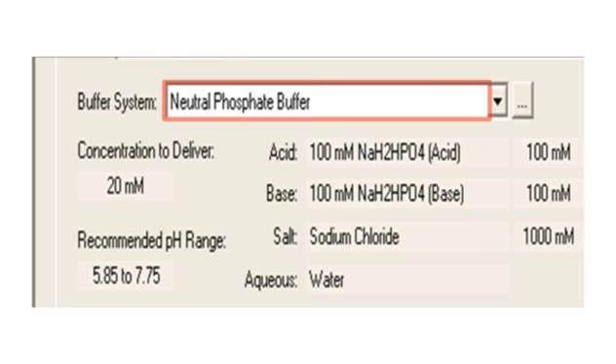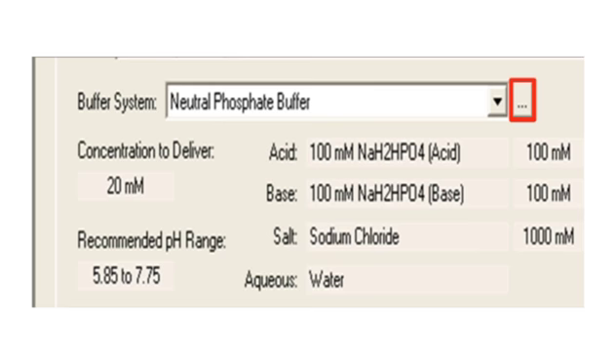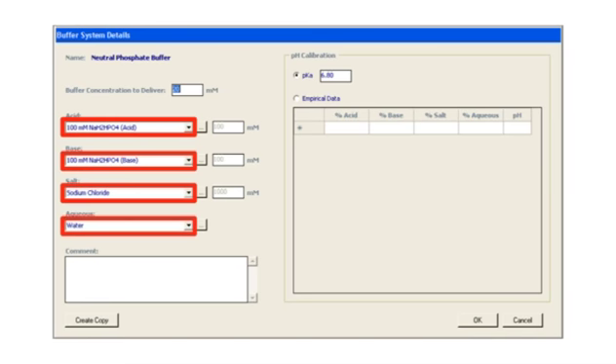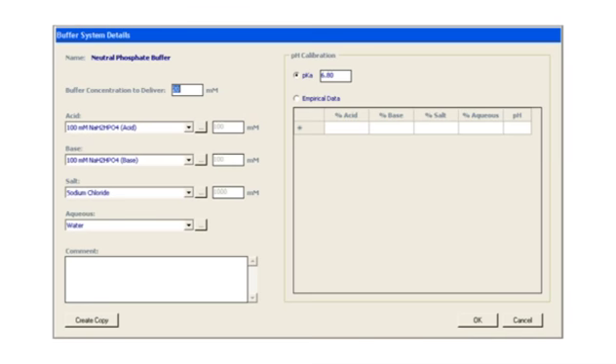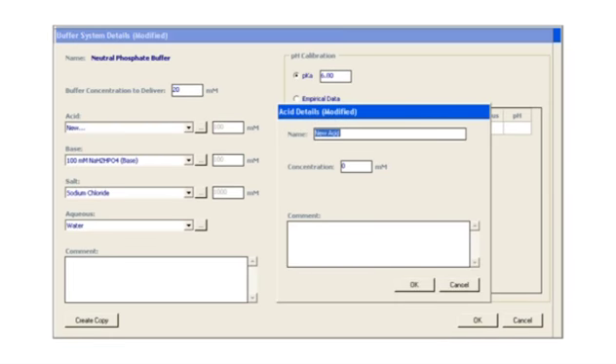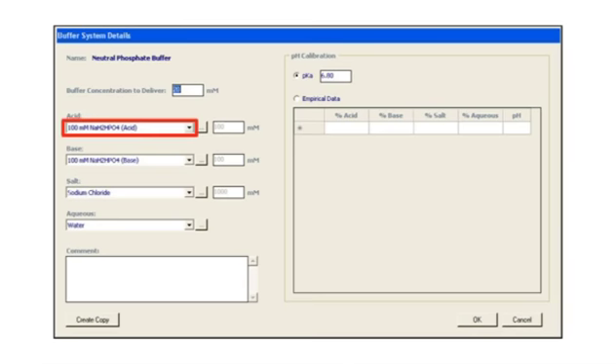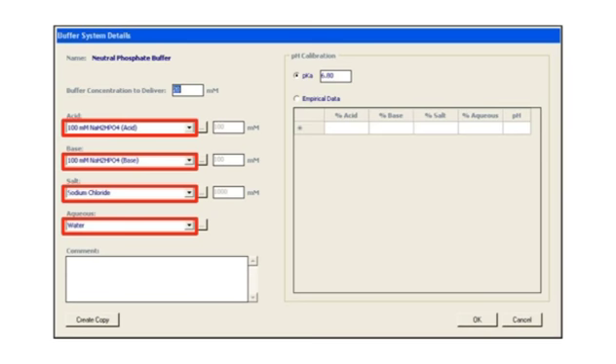Let's look at how a buffer system is defined. The button next to the drop-down menu takes us to the buffer system editor. In this editor, we can enter the desired total buffer concentration and specify the identity and concentration of the solutions in the four named reservoirs. These names are chosen from a drop-down list drawn from a library of defined buffers and salts. New solutions may be added by choosing New from the drop-down list. A new buffer name may then be entered along with the concentration at which it is prepared. The comment field is a convenient place to enter the exact recipe used to prepare the buffer. We select the four elements of the mobile phase: the acid, the base, the salt, and the aqueous. At this point we are only defining those four names; they are not intrinsically associated with a particular physical solvent line.